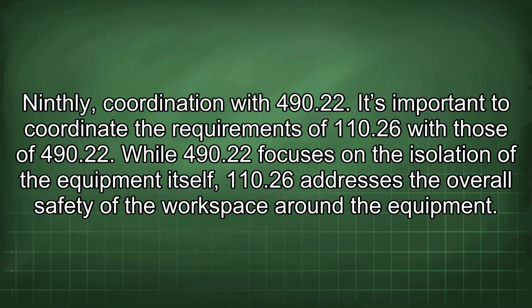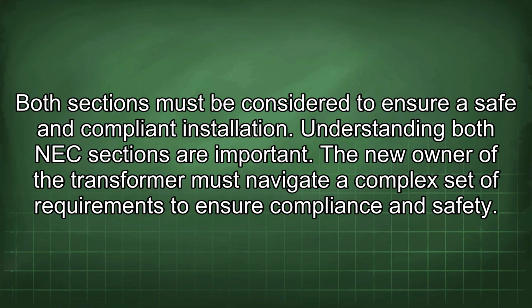490.22. It's important to coordinate the requirements of 110.26 with those of 490.22. While 490.22 focuses on the isolation of the equipment itself, 110.26 addresses the overall safety of the workspace around the equipment. Both sections must be considered to ensure safe and compliant installation. Understanding both NEC sections is important.